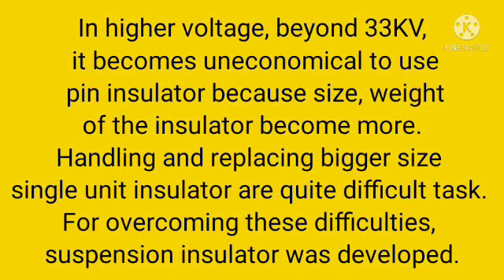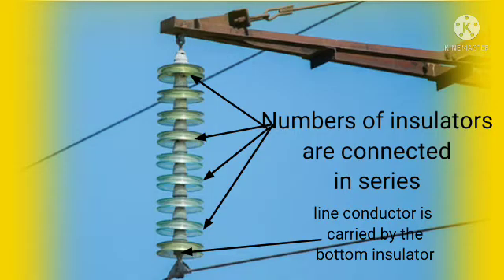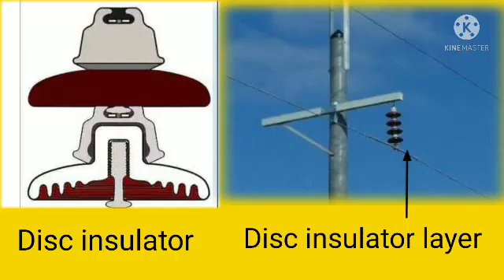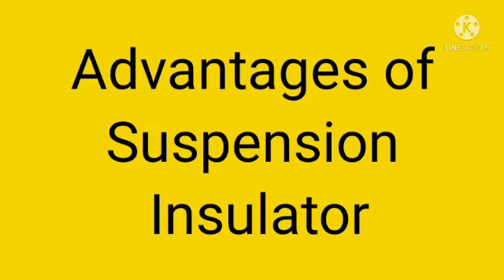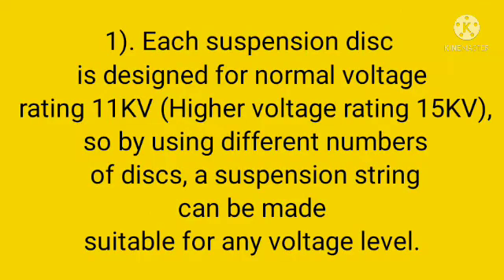To overcome these difficulties, suspension insulators were developed. In a suspension insulator, a number of insulators are connected in series to form a string, and the line conductor is carried by the bottommost insulator. Each insulator of a suspension string is called a disc insulator because of its disc-like shape.